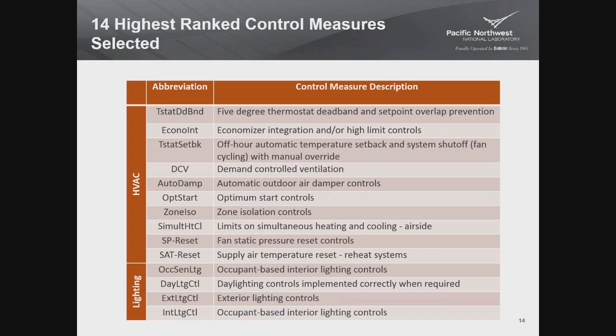Supply air temperature set point. I mentioned that the air is coming out of the air handler at some cold temperature, typically 55 degrees, and then maybe reheated up to 90 or 95 degrees in zones that need heating. This requirement includes logic that looks at the conditions of all the zones. So if no zones require cooling, why supply 55-degree air and heat it again? It doesn't do that. It will raise that supply air temperature as high as possible to still meet the loads in the building. So one zone may be in cooling, but not full demand cooling. So maybe you get away with 60 or 62-degree air. That means that the zones that are in heating have to heat that air up less.